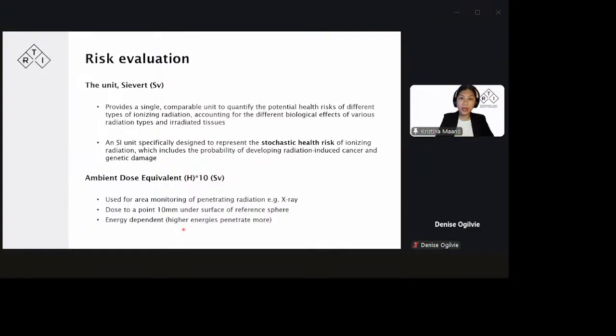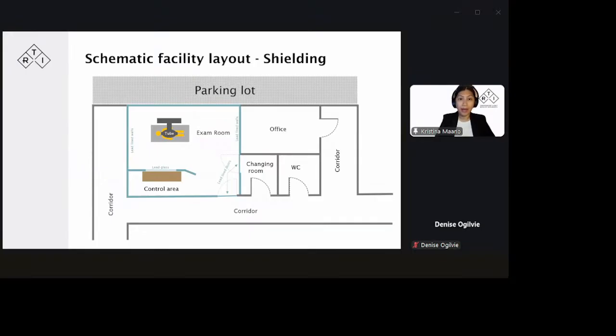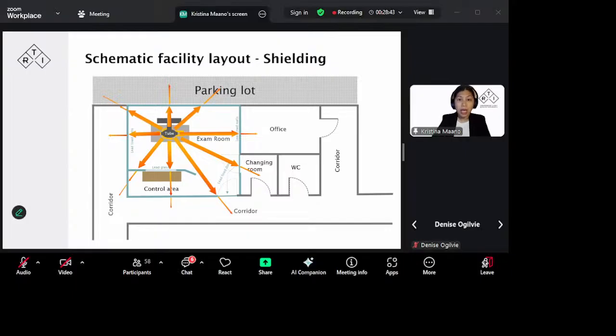So since we're talking about risk evaluation, to reduce the risk, I believe many of us are aware or perhaps already have been involved in doing shielding calculations. So in the X-ray room, we typically use a lead lining, or we do solid concrete, and this is done during the design phase and the calculations are based on the equivalent lead thickness standard of lead glass. So usually, during the shielding calculation, there's already a safe margin, making sure that the stray radiation does not penetrate through the shielding.